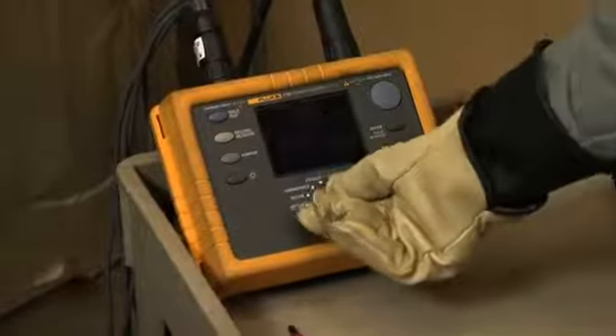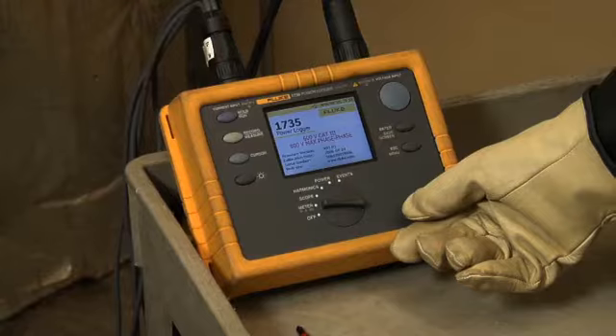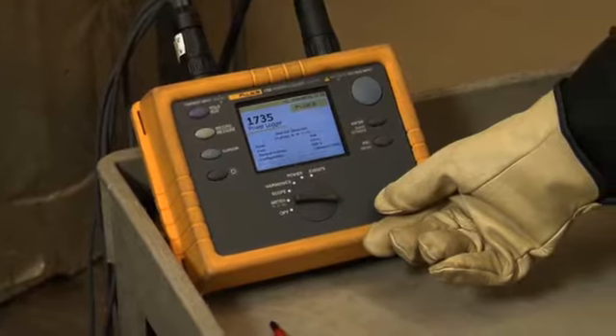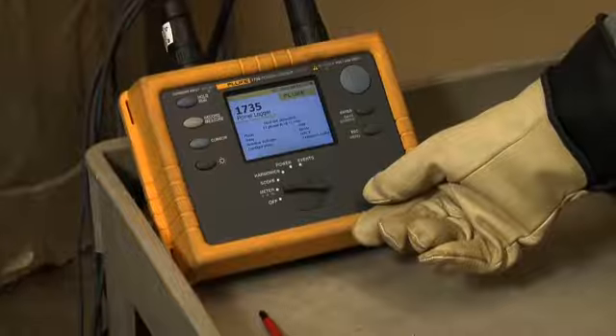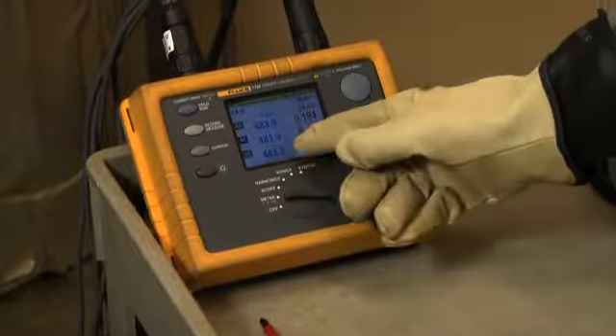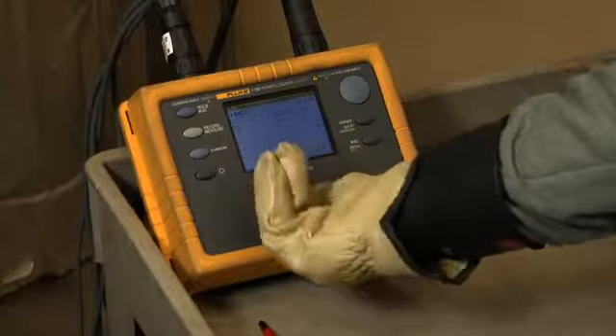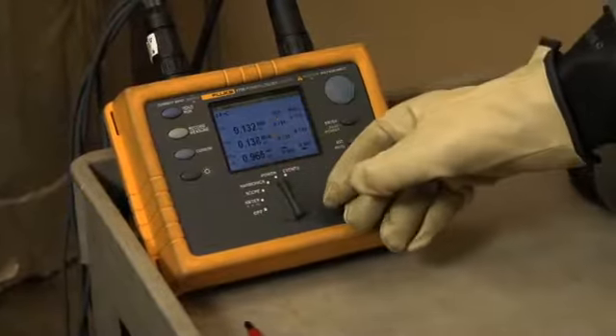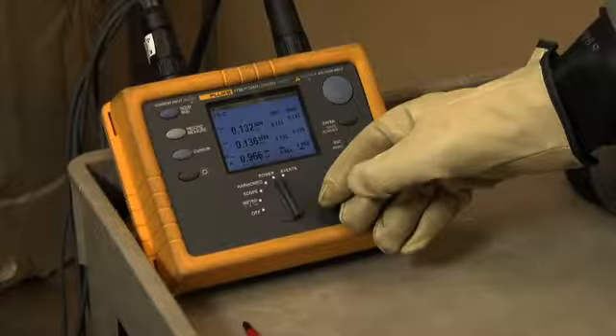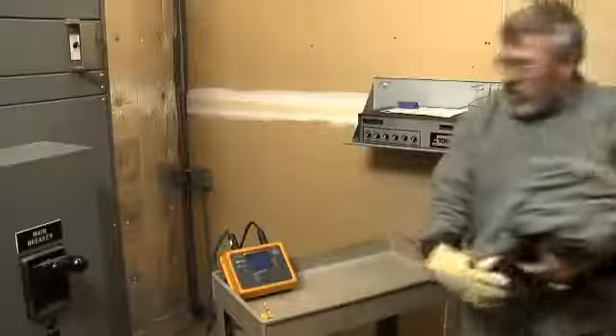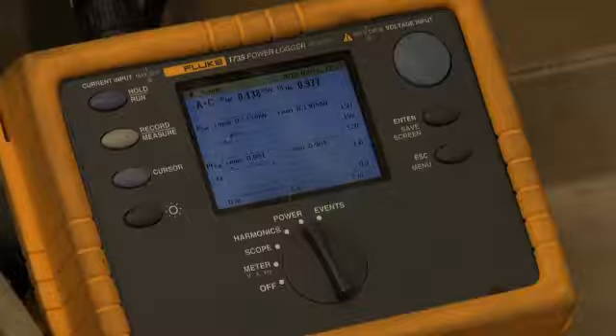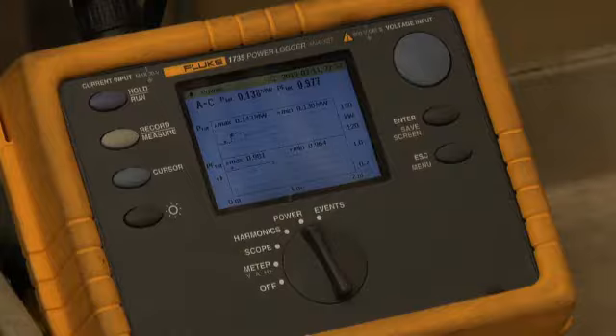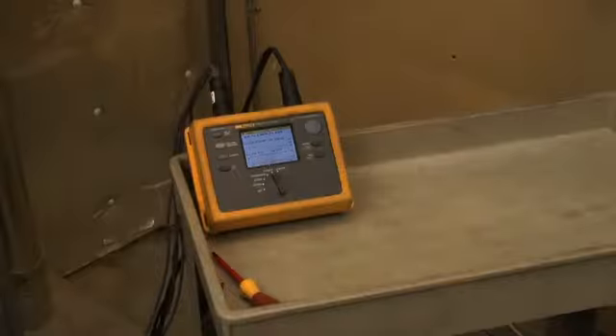When you're preparing to leave a logger behind for an extended time period, you want to make sure you're capturing the correct data. You can check this by turning the dial on the Fluke 1735 power logger to meter. The Fluke 1735 power logger automatically captures all of the major power parameters while it logs. In this case, we're focused mostly on power factor. Start recording and walk away. You want to capture the full demand cycle if at all possible, in particular, a full average 7-day week. You will get the best information if you can document the state of the power supply under all of the different operating conditions that occur in the facility.